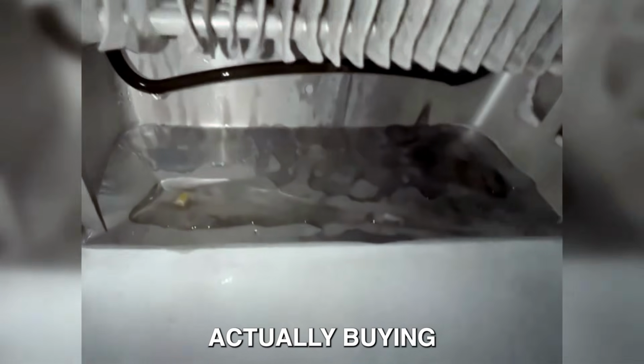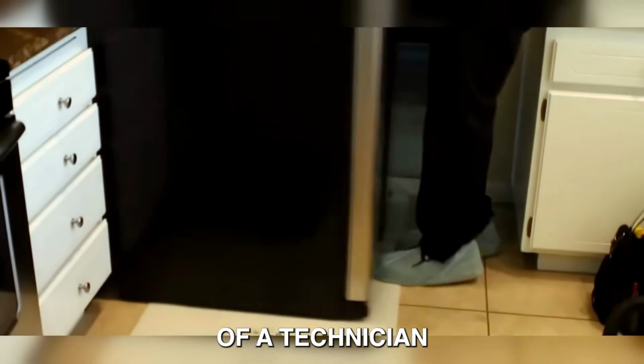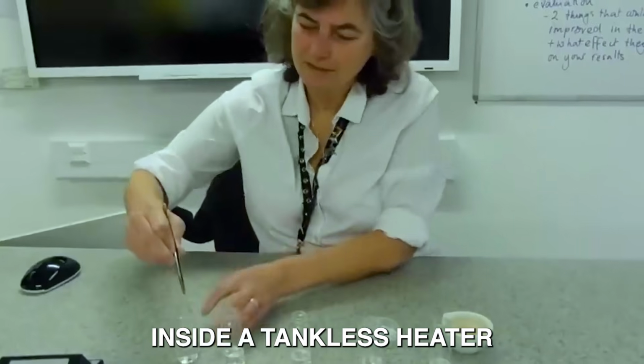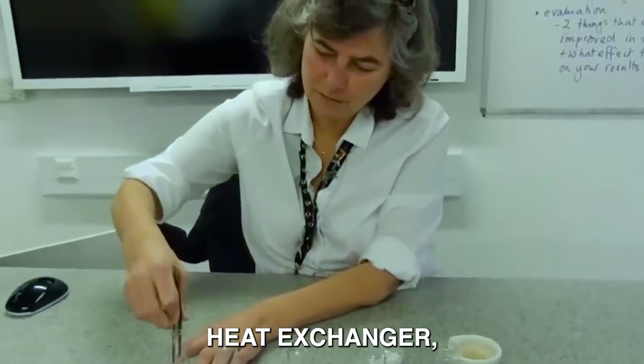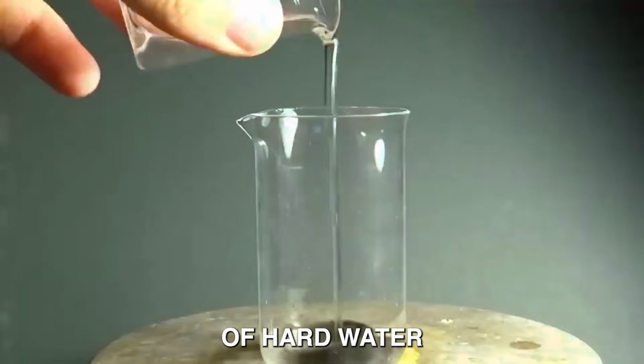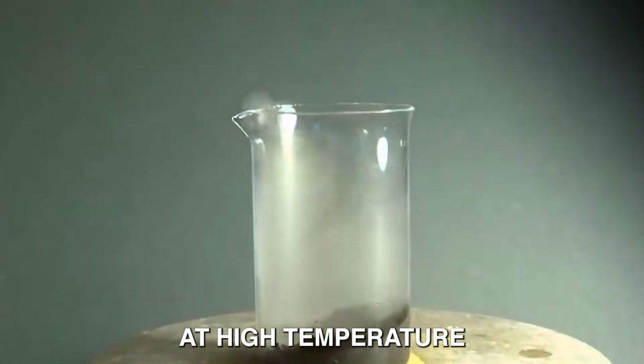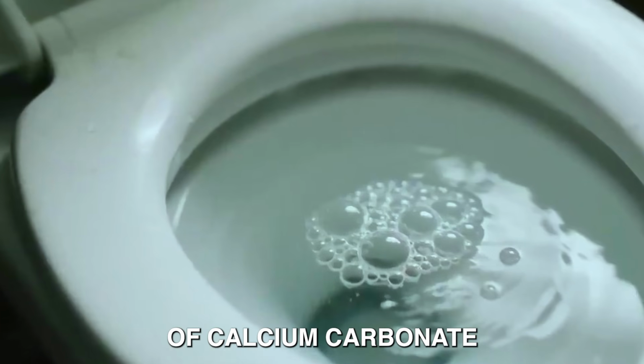What you are actually buying is 40 minutes of a technician standing next to a bucket. Inside a tankless heater sits a copper heat exchanger, and every gallon of hard water passing through it at high temperature leaves a ring of calcium carbonate inside that coil.